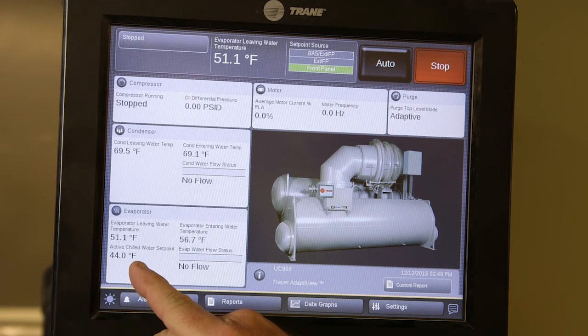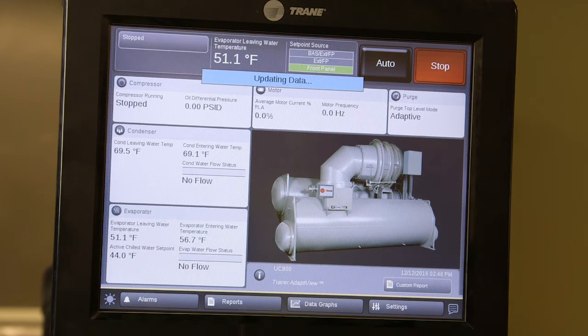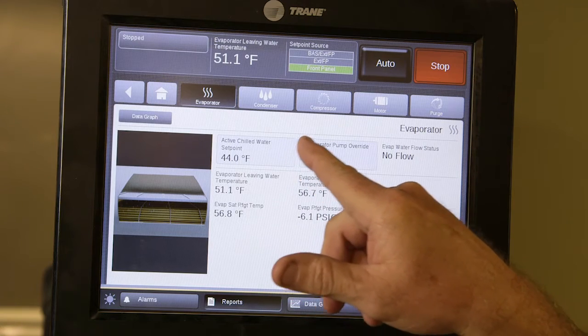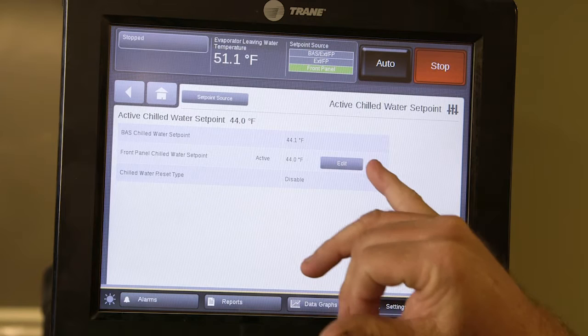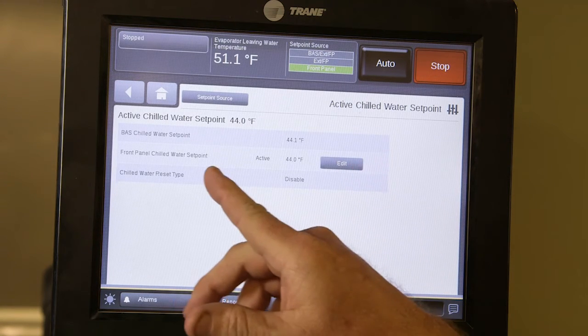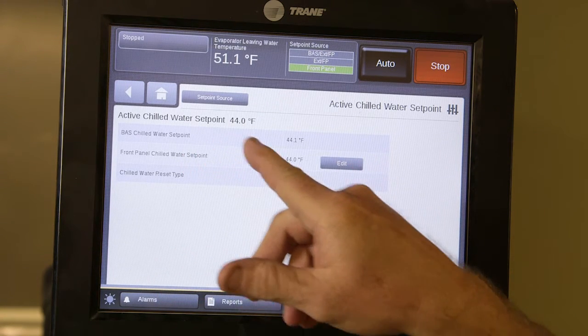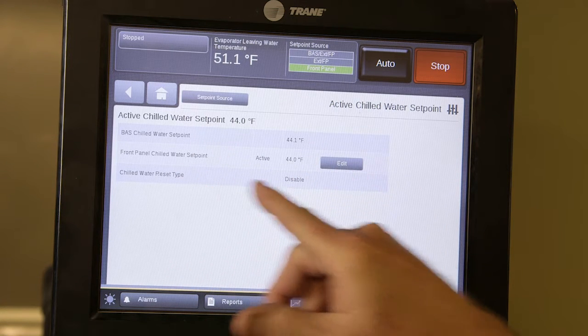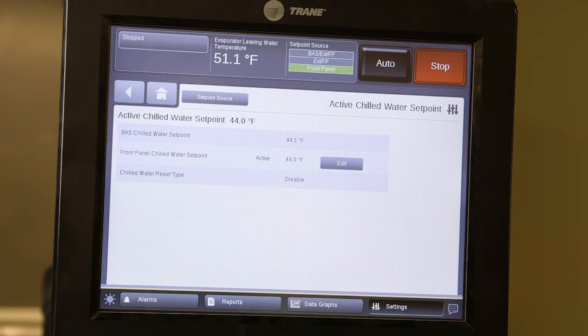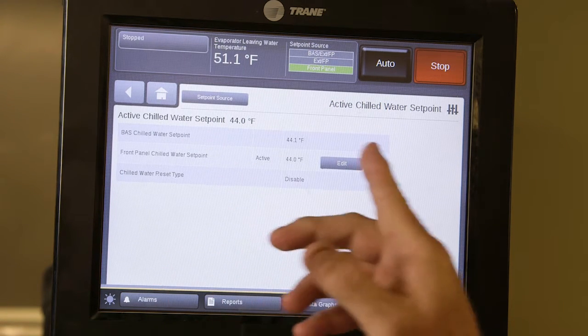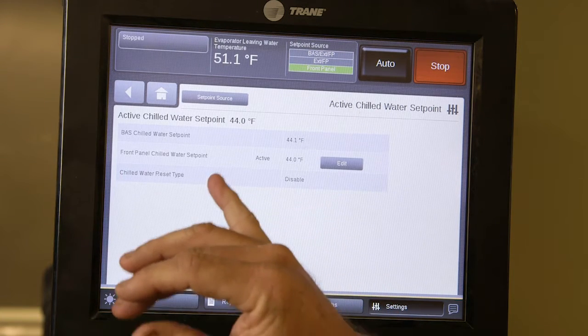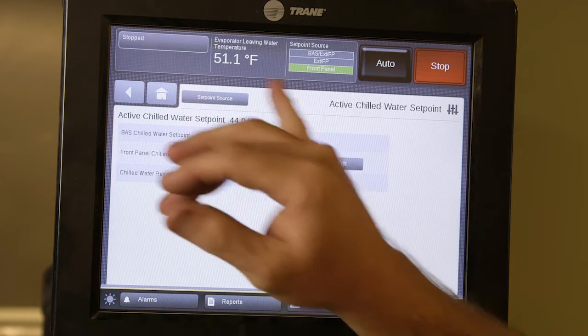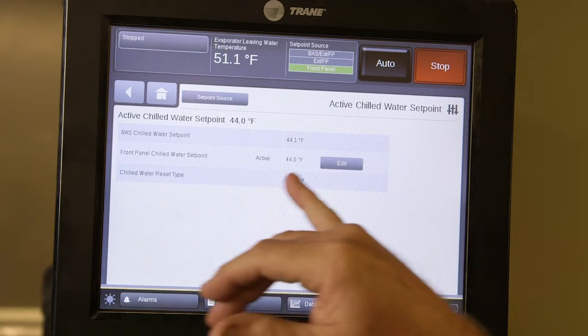You can change the chilled water set point at any time by clicking on it, going to the active chilled water set point menu, clicking on that, then selecting Edit to raise or lower it. It will also tell you whether it is active for BAS control or front panel chilled water set point — right now it's set up for front panel. After you edit and change the set point to whatever user-defined value you need, press the acknowledge button and it will take effect.